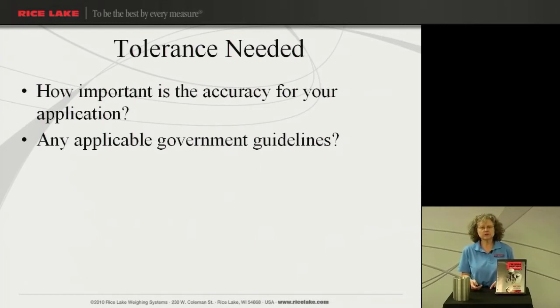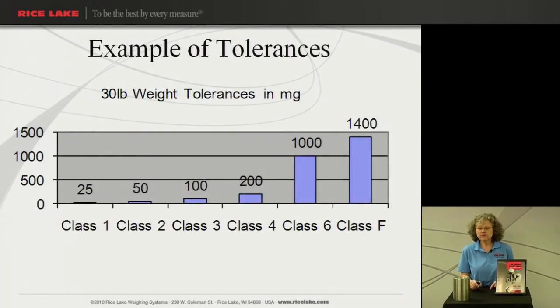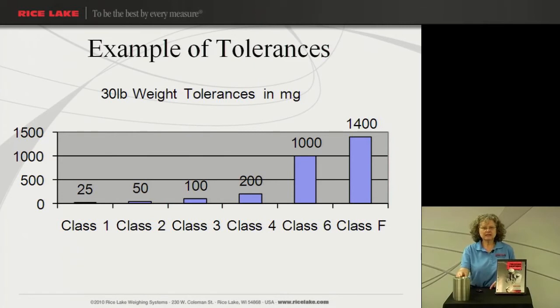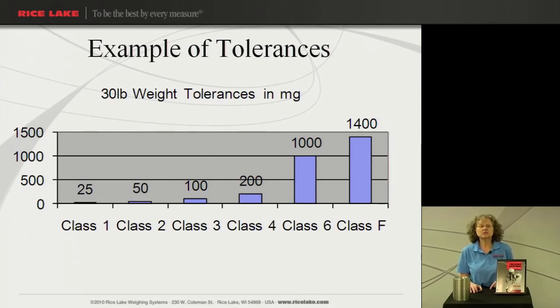Let's look at a particular reference here. In front of me I have a 30-pound stainless steel weight. This can be purchased in many different classes — for example, you could purchase this as a class 1, 2, 3, 4, 6, or class F weight. In this chart, we list the different tolerances in milligrams: class 1 is 25 milligrams, class 2 is 50, class 3 is 100, class 4 is 200, class 6 is 1,000 milligrams, and class F is 1,400. Think about what you're weighing and the balance resolution you might be using this weight on.